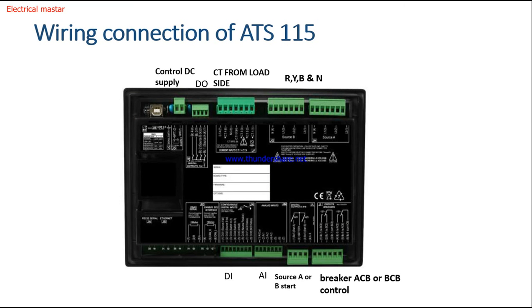Now we will see the wiring connection. The wiring connection is also very simple. This is the backside of the controller panel. You can see it needs the 24 volt control supply from the battery. You have to connect it here, and this is for the digital output purpose. Here you have to connect the CT from the load, the outgoing cable load, for measuring the current. And here you have to connect the source A and source B voltages with the neutral line.